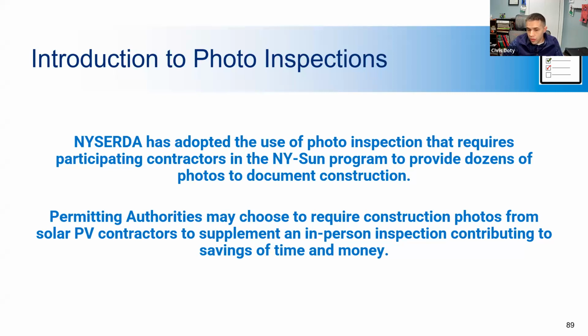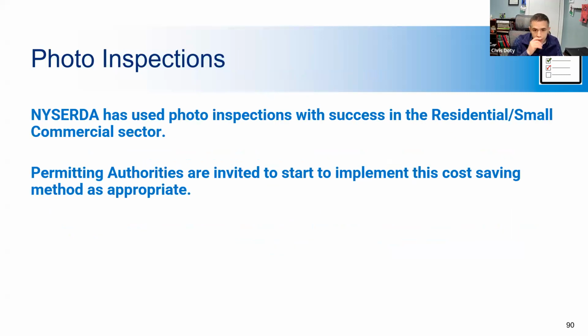Photos can tell a story of how things were constructed and save the inspector time. It can improve inspector safety by reducing the exposure to hazards, like I mentioned earlier. Like they may not have to go up on ladders or access energized electrical equipment if there's photos of the equipment. You can have photos of trenches and walls before being closed to reduce the number of trips to the site. So it can be a very useful way to do inspections or supplement inspections to help save time and money.